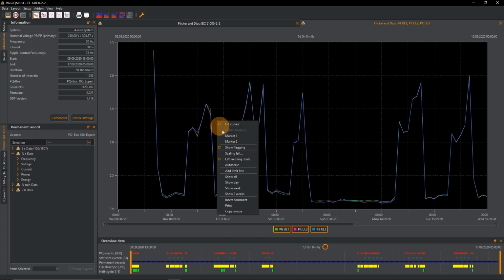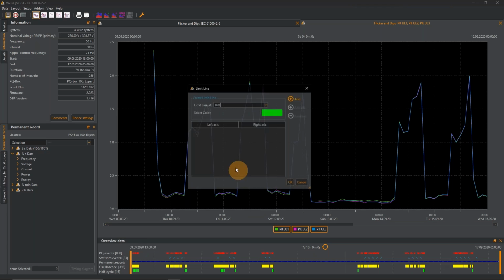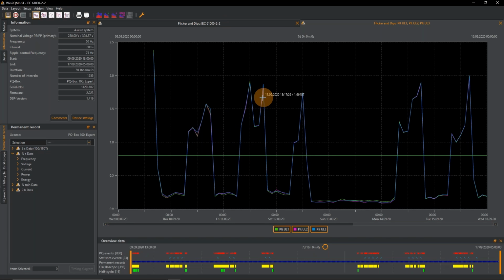I will display some limit values. With a right click, I can add the limit line, and this immediately adds the proposed limit line of the standard I've chosen. So in this case, IEC 61000-2-2. I will open it and see, okay, the limit is at 0.8. Long-term flicker doesn't have a unit, so there's actually just 0.8, no amps, no volts, nothing, just 0.8.